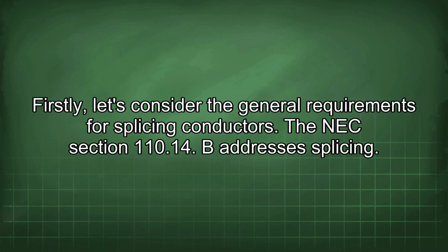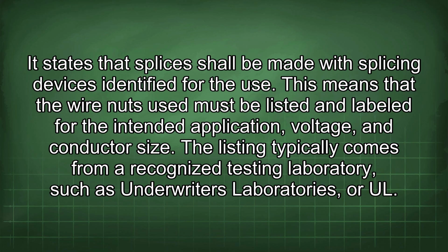Firstly, let's consider the general requirements for splicing conductors. The NEC section 110.14 B addresses splicing. It states that splices shall be made with splicing devices identified for the use. This means that the wire nuts used must be listed and labeled for the intended application, voltage, and conductor size. The listing typically comes from a recognized testing laboratory such as Underwriters Laboratories, or UL.